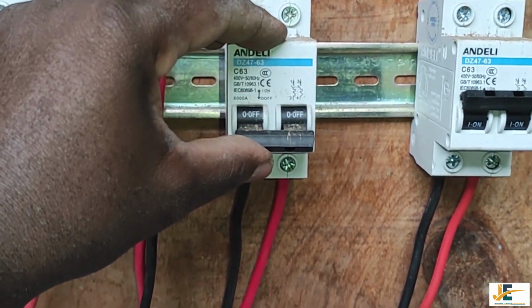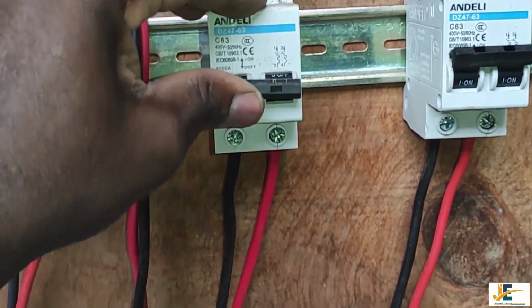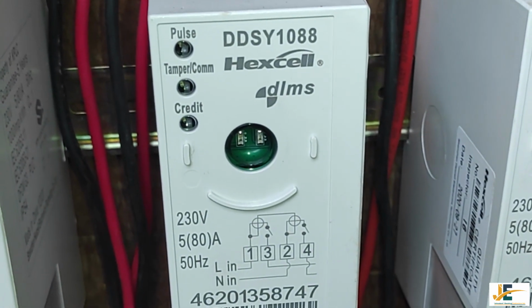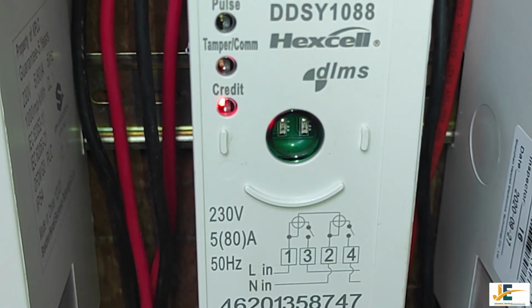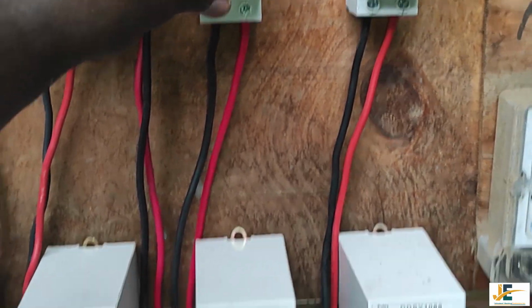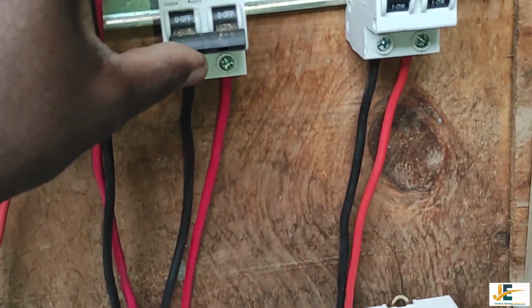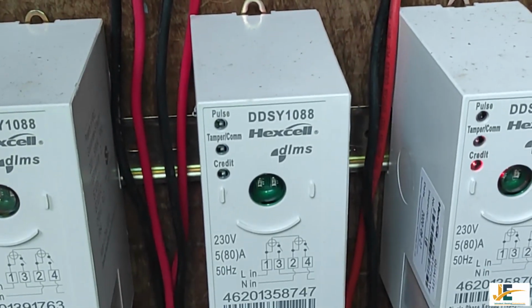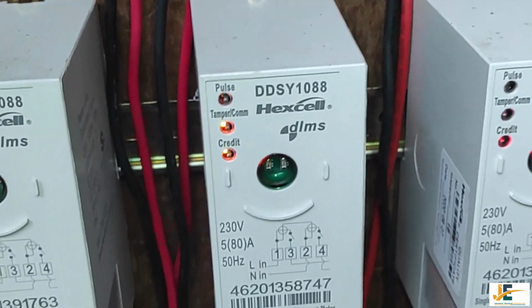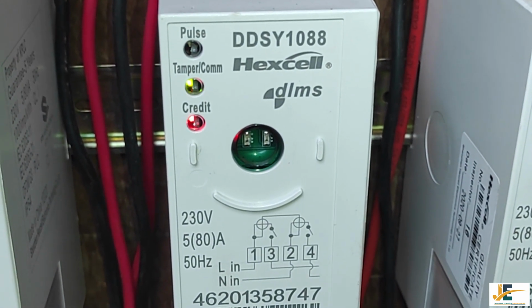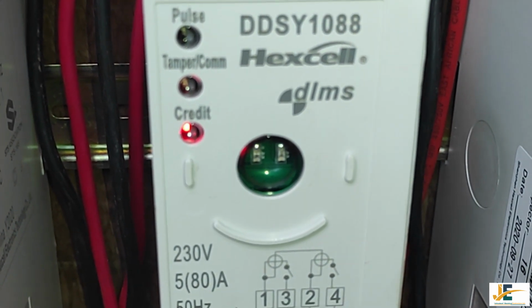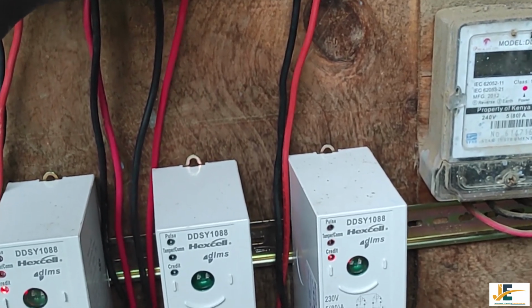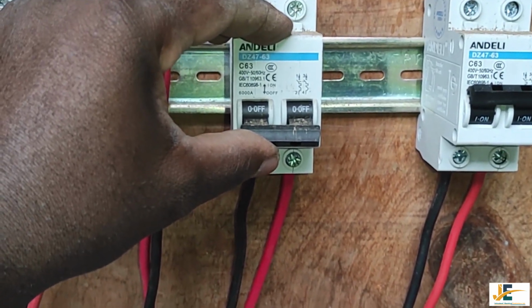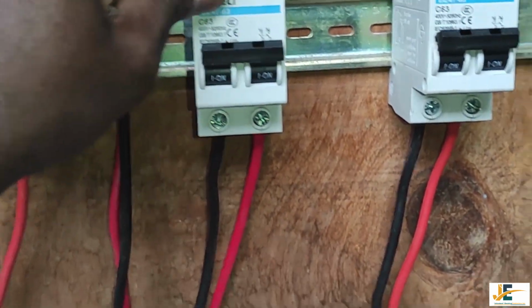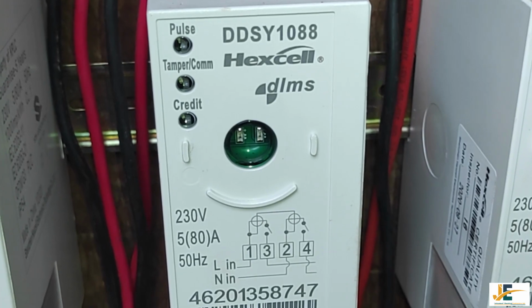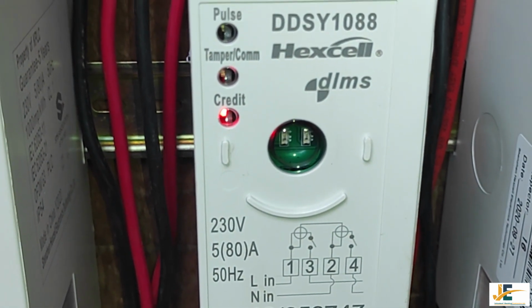So the next step will be powering our meters. You put our double pole MCB double pole on, and our meter is now powered. You can see on the front side there is pulse, tamper, and credit indicators. This is communication, and as I said, this MCU communicates with the CIU through PLC. So that's done.